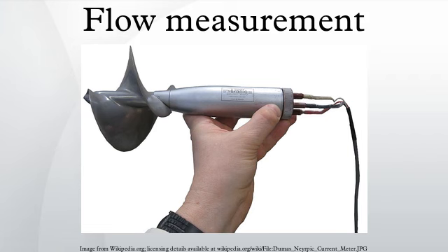Turbine meters are generally available for 4 to 30 cm or higher pipe sizes. Turbine meter bodies are commonly made of bronze, cast iron, or ductile iron. Internal turbine elements can be plastic or non-corrosive metal alloys. They are accurate in normal working conditions but are greatly affected by the flow profile and fluid conditions.